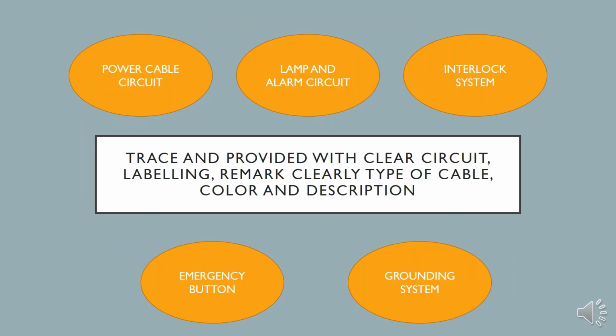For this laboratory one, we have to trace and provide a clear circuit labeling, remarking clearly the type of cable, color and description of each type of circuit. There are 5 circuits we have to elaborate, which are power cable circuit, lamp and alarm circuit, interlock system, emergency button and grounding system. Each type of circuit has a different purpose and its own different safety requirement.